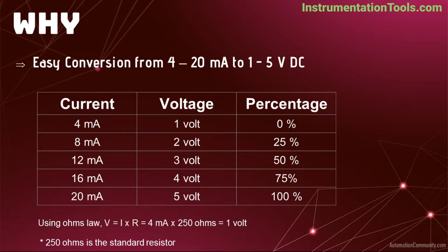Why do we need to convert 4 to 20 mA into voltage? The 4 to 20 mA signals are connected to analog input modules of the PLC. The analog input module consists of analog to digital converters, ADC. This ADC needs voltage as an input signal and converts it into equivalent binary signals, 1s and 0s. The analog input module then provides the equivalent binary signals to the PLC processor, CPU, for further operations.